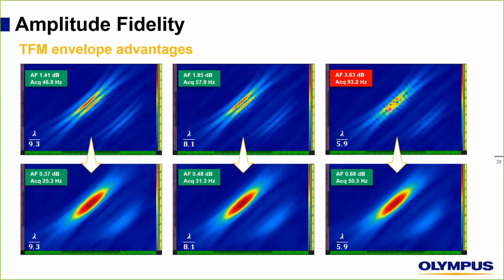For this case, we have an amplitude fidelity of 3.63 dB, and an acquisition rate of 93.2. So this is a good case where our setup is not complying with the code. By applying the envelope, amplitude fidelity became 0.88, which is complying with the code. Of course, we are losing some speed of scan here. This is for a resolution of 5.9 points per lambda.